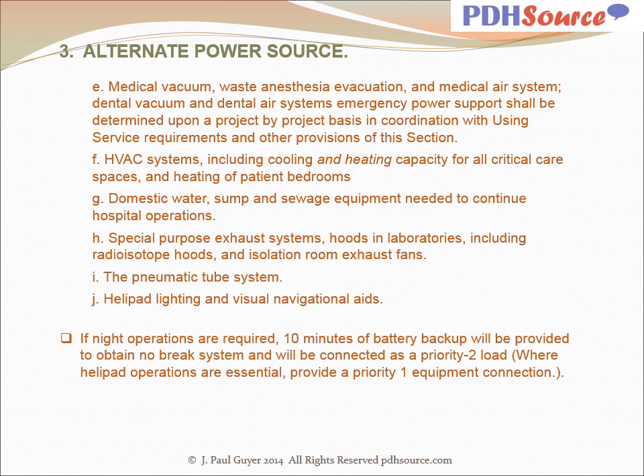Medical vacuum, waste anesthesia evacuation and medical air system, dental vacuum and dental air systems emergency power support shall be determined upon a project-by-project basis in accordance with the using service requirements and other provisions of this discussion. HVAC systems, including cooling and heating capacity for all critical care spaces and heating of patient bedrooms. Domestic water, sump, and sewage equipment needed to continue hospital operations. Special purpose exhaust systems, hoods in laboratories, including radioisotope hoods and isolation room exhaust fans.